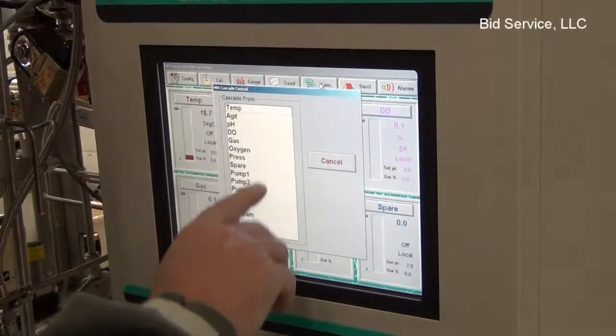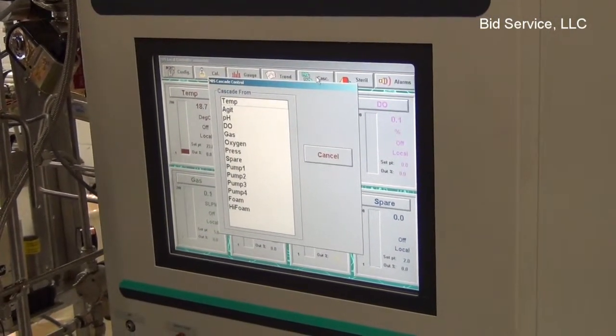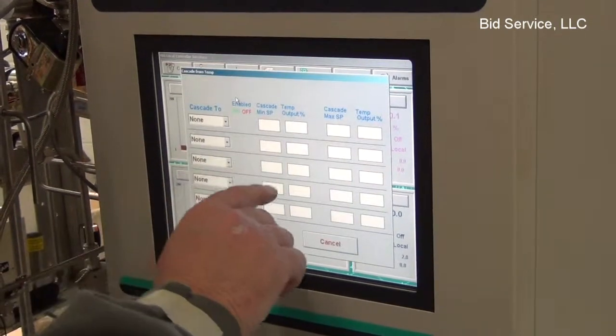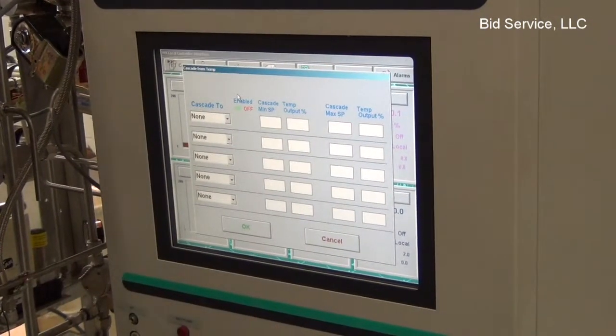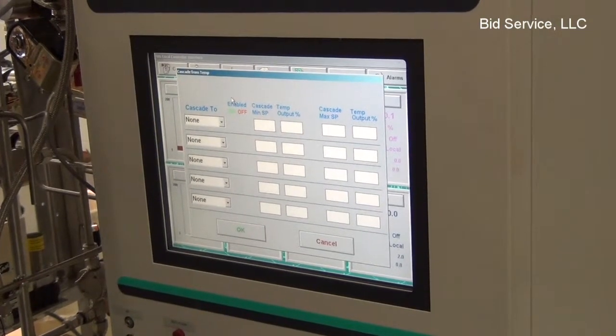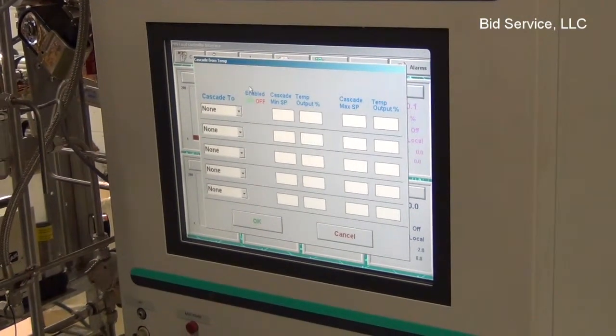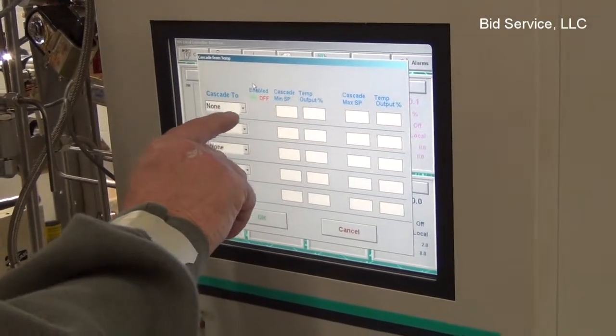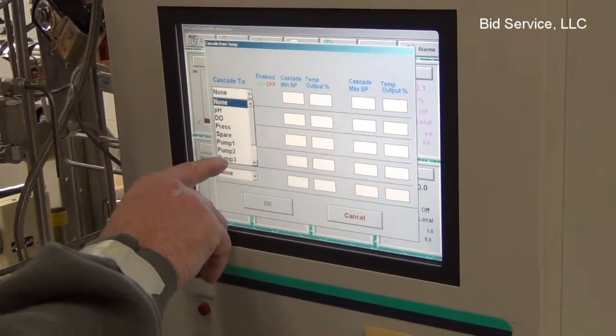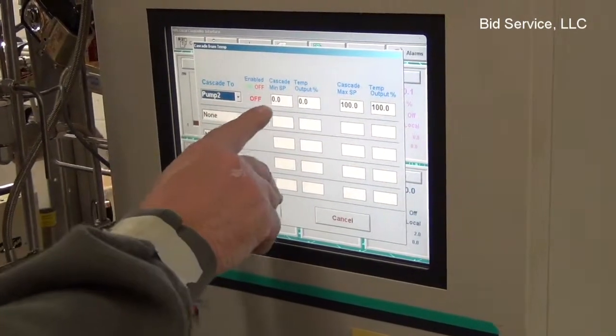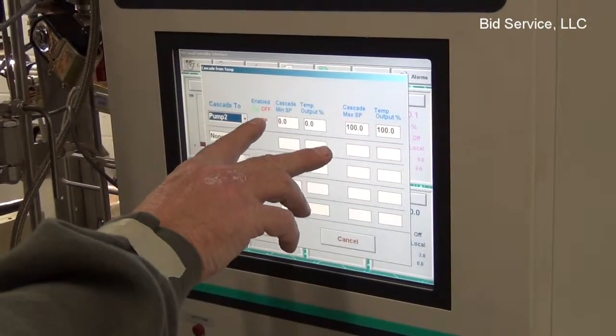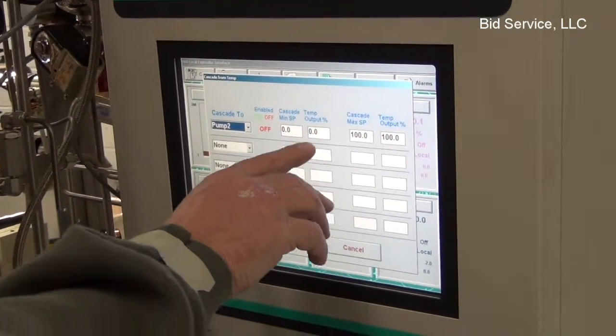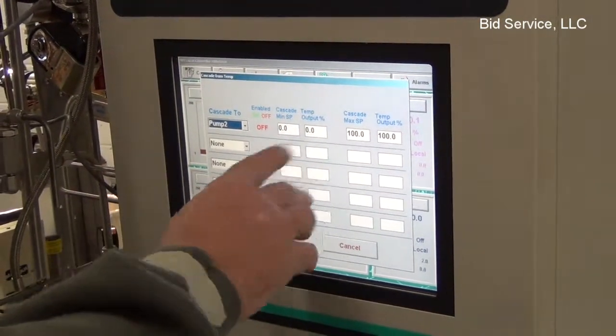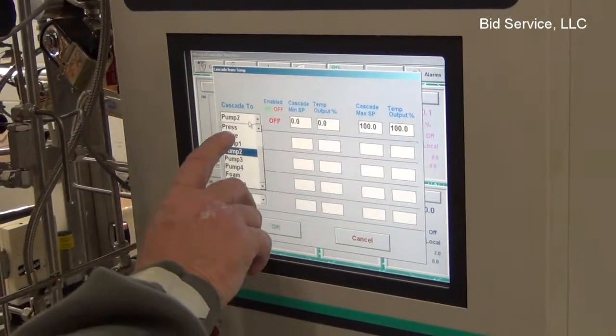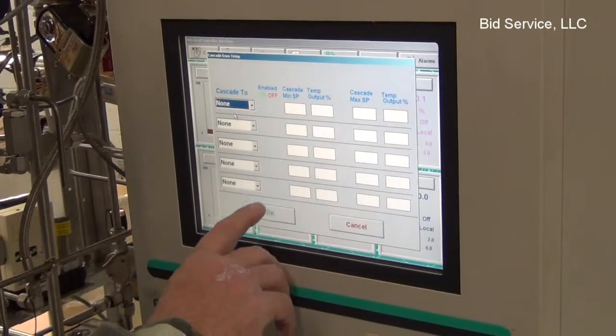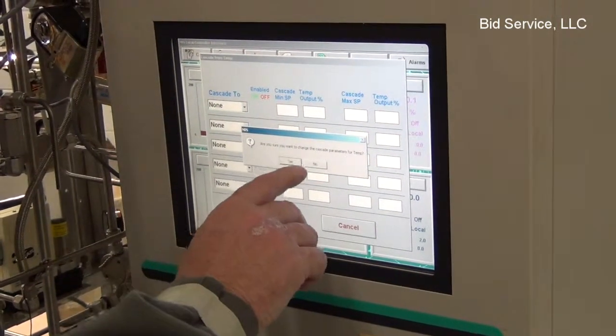I go under cascade. Again, all your loops are here. You can go to a loop, for instance, a temperature loop, and you can cascade to some other components in here so that some things turn on and turn off at certain conditions that you've previously set. So for instance, if I wanted to cascade to a pump, I could just hit pump 2, and I can enable it or disable it, the minimum setting, the maximum setting, if it's an output percentage, you put it in there, etc. I'm going to change that back to none. Say OK. Yes.